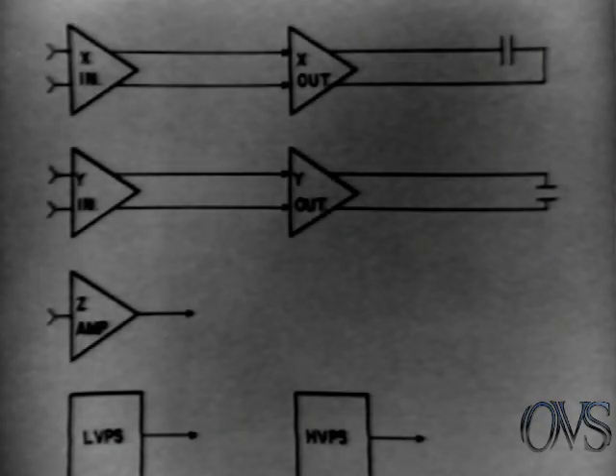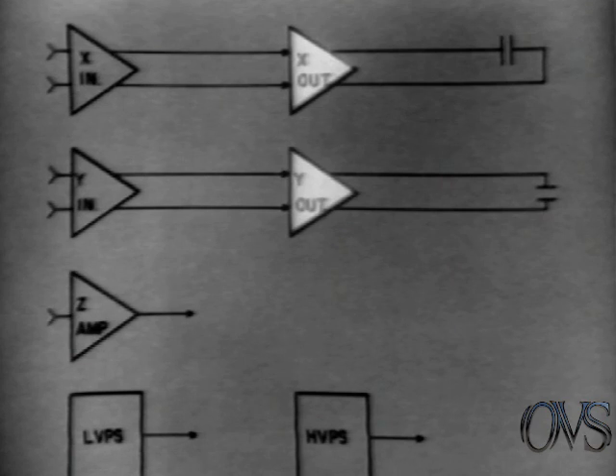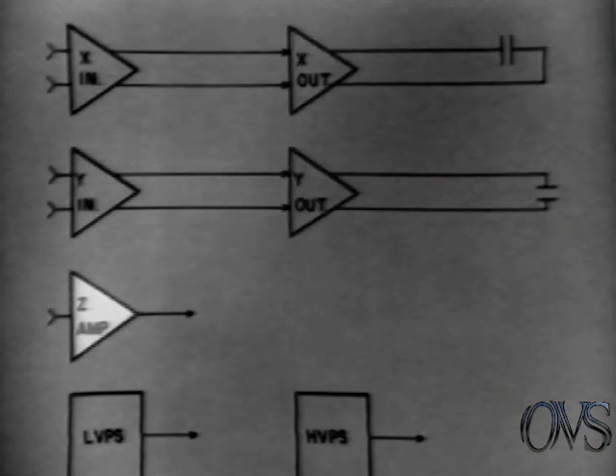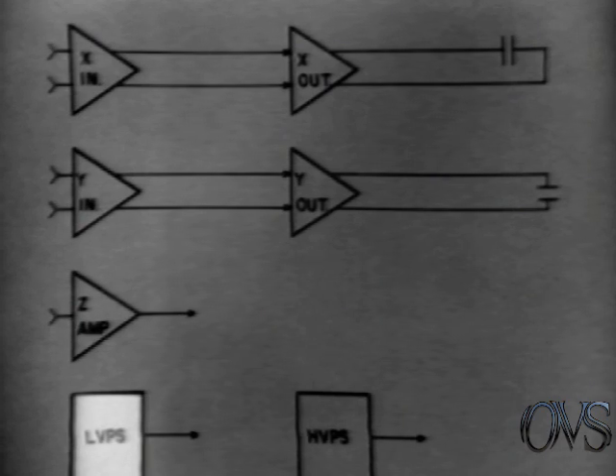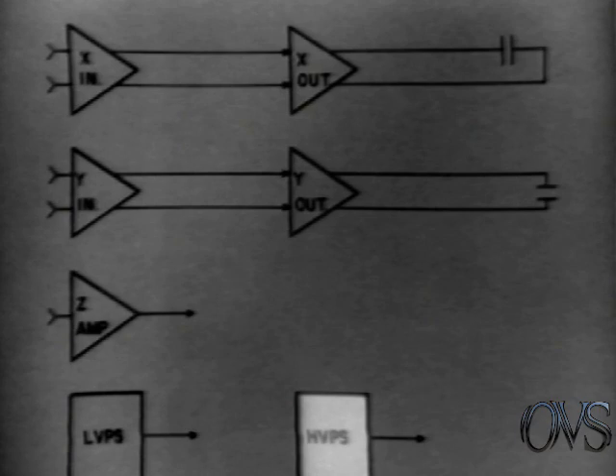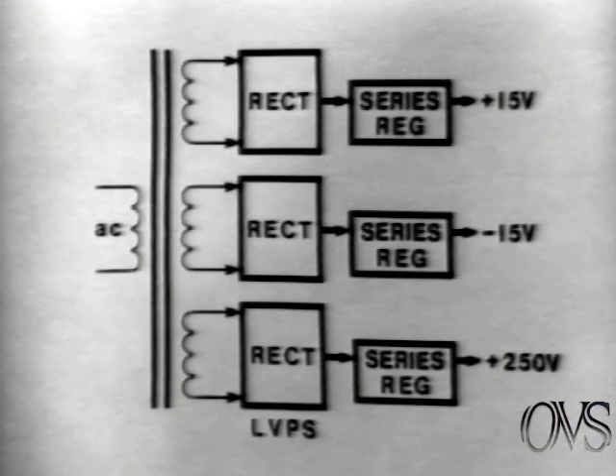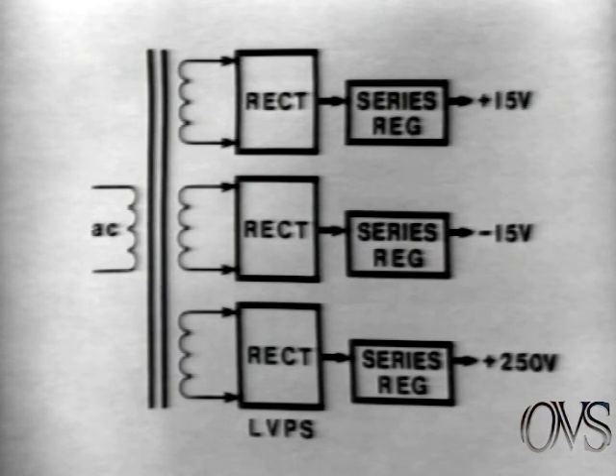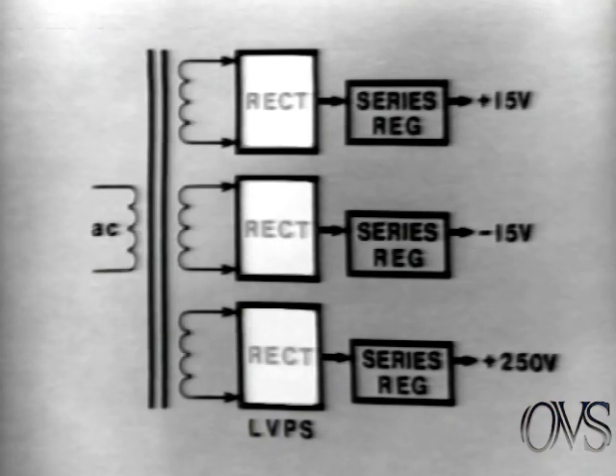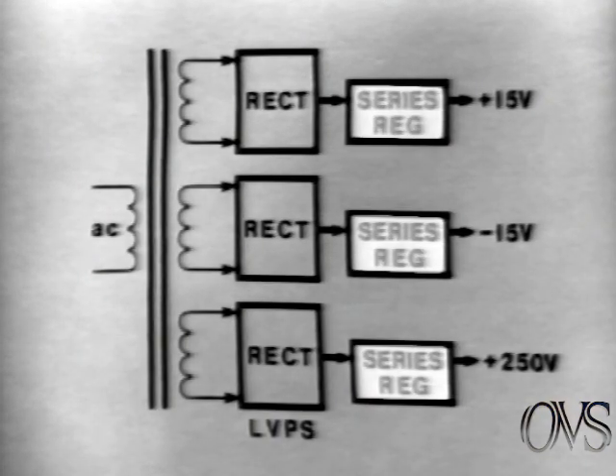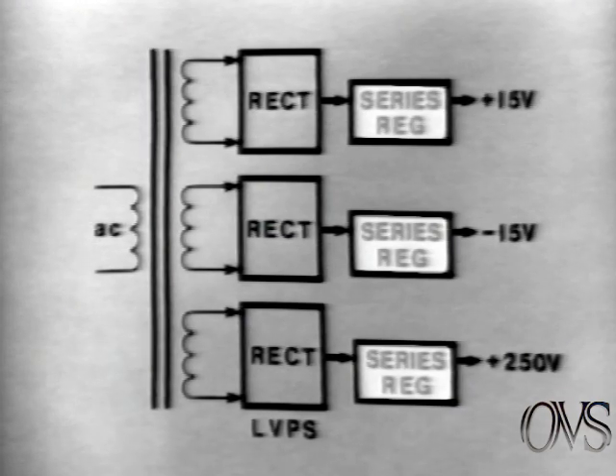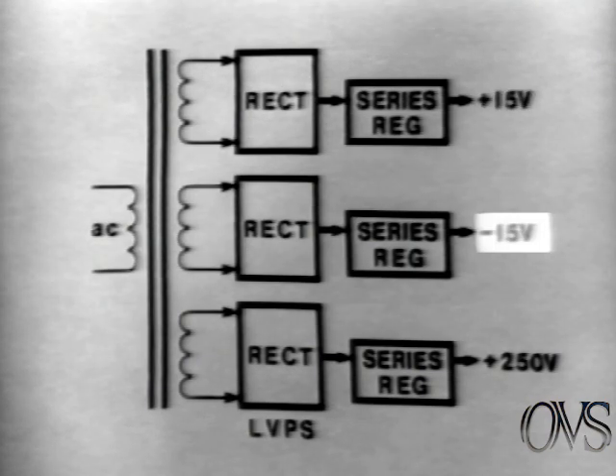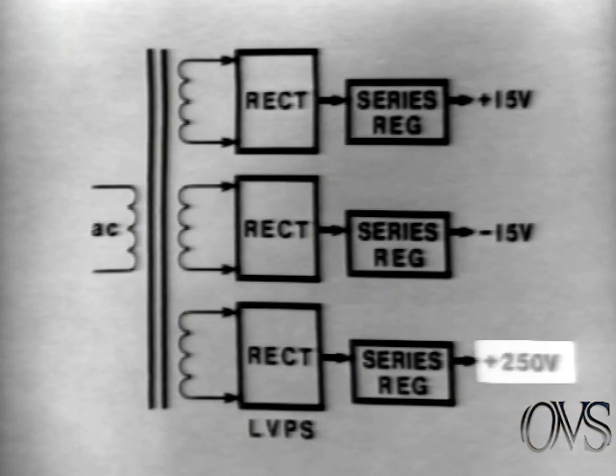Now let's discuss signal flow. Here's a simplified block diagram showing the X and Y-axis input and output deflection amplifiers, the Z-axis amplifier, which provides intensity and blanking control for the CRT, a low voltage power supply, and a high voltage power supply. The low voltage power supply is a standard regulated supply configuration. The AC line voltage is stepped up, rectified, and applied to series regulating devices which maintain constant output levels regardless of line or load variations. The low voltage supply provides plus 15 volts, minus 15 volts, and plus 250 volts.